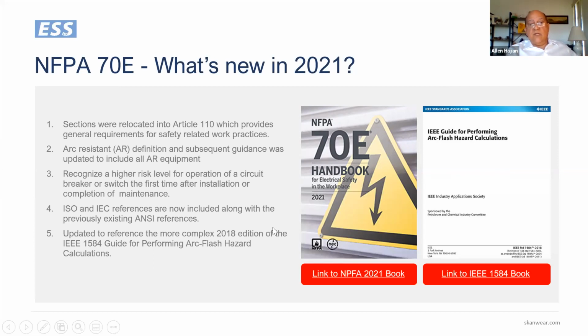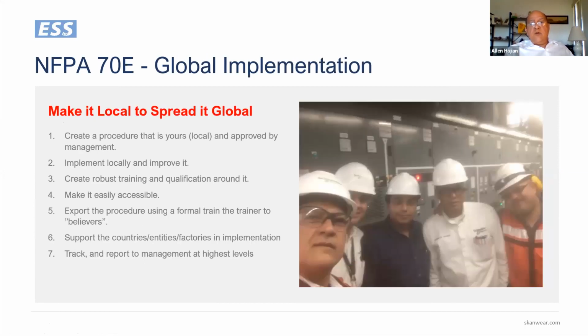I went through the new version. It says that the arc resistant equipment has been expanded from just medium voltage, or voltages between 600 volts and 15,000 volts, to all equipment that meets the arc resistant definition. It recognizes a higher risk for operating a circuit breaker or a switch after the first time installation or maintenance. It adds ISO and IEC references, and it updates the calculation to the new version of the 1584. How do you make this global?